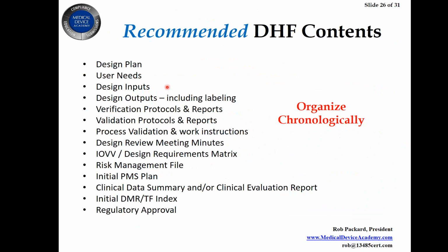As I said, at the beginning of design transfer, you might start writing a post-market surveillance plan. It might be a draft, and then you finalize it when you launch the product. That might include post-market risk management data collection. You might have a clinical data summary if you do a clinical study, or a clinical evaluation report if you're doing a literature search route, or a combination of the two.